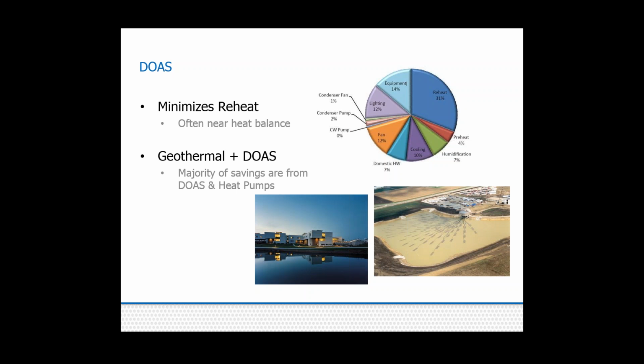But one of the biggest savings is that a lot of times, in Iowa it's kind of cold, and you've got a little heat being generated by the lights and the patient and maybe a piece or two of equipment and a TV, and you've got cold coming from the outside window and the wall, and you're kind of in temperature balance. So the only thing that's happening is you're ventilating and the fan is running in your heat pump, but the compressor isn't necessarily running very often. And I believe that facility is Energy Star 100, and the last I heard was somewhere below 100 kBTU per square foot per year. And I would say the bulk of those savings are because of the DOAS plus heat pumps.